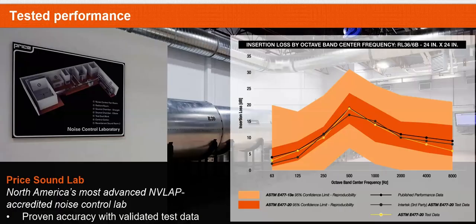Well, every now and then we'll see a submittal that has data that's just so far off of ours, and I wonder if that's it. That is exactly the reason why they are tested to an older standard. We're not saying that our silencers are better. We're just telling you that if you specify under ASTM E477-20, you at least know what you're going to get. Because if I'm a consulting engineer and I see ASTM E something, I'm like, we're good, versus needing to look at the last 2 digits to know if I'm getting the right thing. That's one of those things you just wouldn't know.